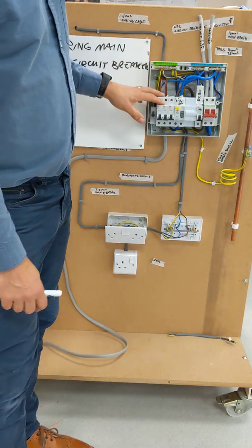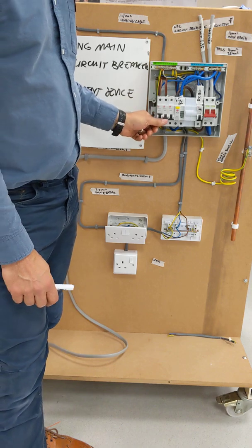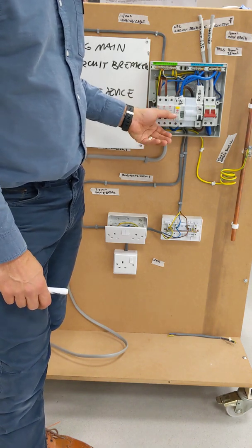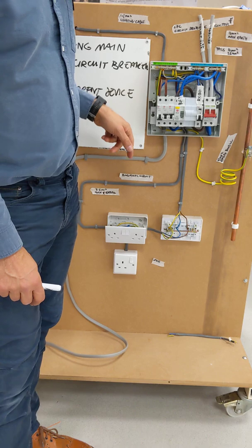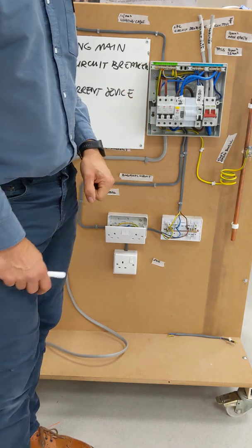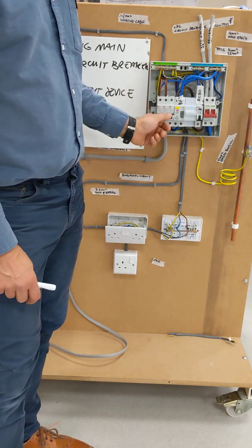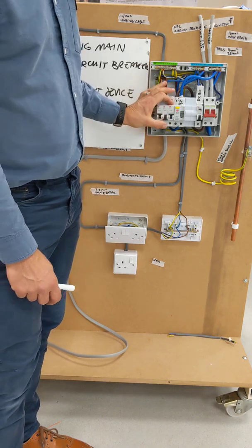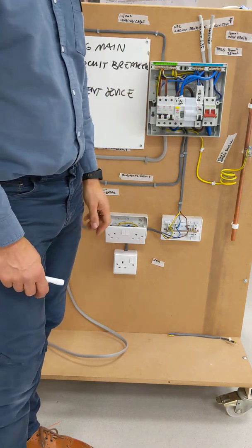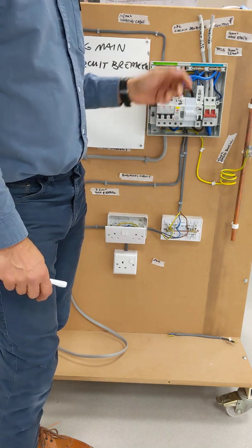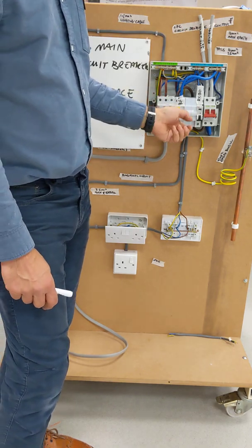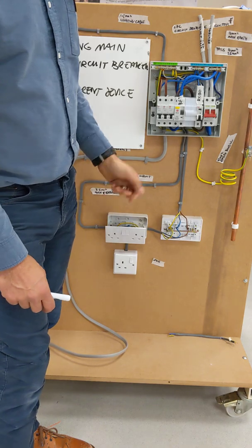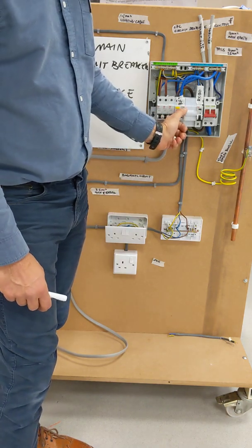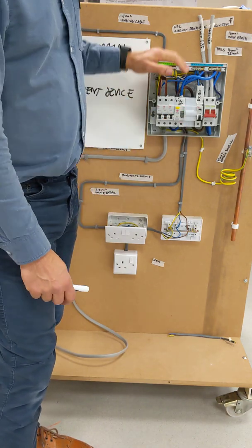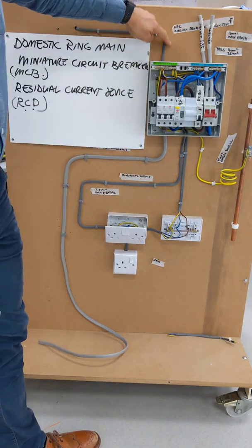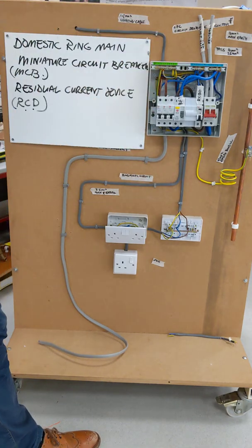So those different devices now are sending power down different parts of our circuit. So I might have a loop connected to my first MCB, which is controlling my lighting downstairs. I might have a loop there on my second MCB, which is controlling my lighting in another part of the house. And I might have another one for my ring main that's in the kitchen, my ring main in the bathroom, whatever. So I'd probably be creating my RCD to have my ring main going to the bathroom, giving more protection against electric shock in a wet environment. So all those things, you can see how they're connected together and how they would send the power off down different parts of our ring main.